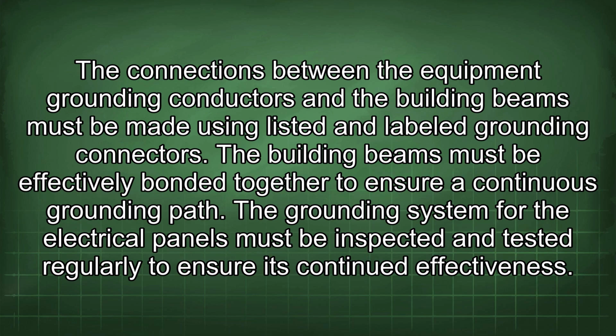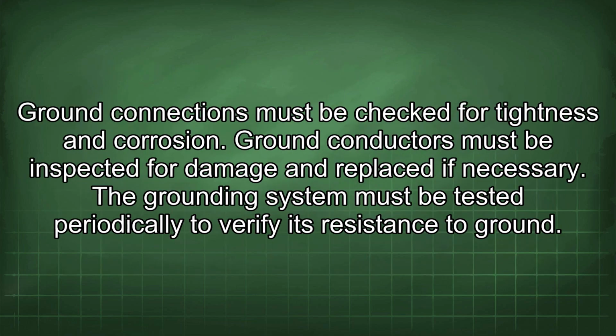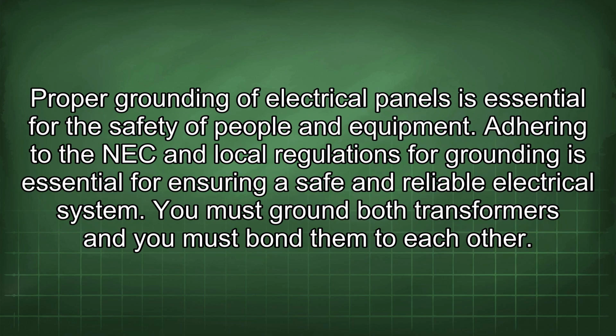The grounding system for the electrical panels must be inspected and tested regularly to ensure its continued effectiveness. Ground connections must be checked for tightness and corrosion. Ground conductors must be inspected for damage and replaced if necessary. The grounding system must be tested periodically to verify its resistance to ground. Proper grounding of electrical panels is essential for the safety of people and equipment. Adhering to the NEC and local regulations for grounding is essential for ensuring a safe and reliable electrical system.